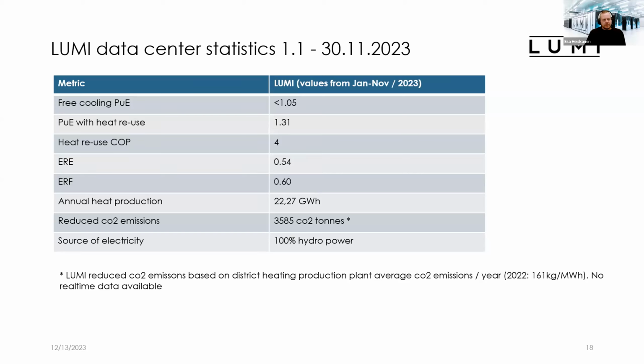Heat reuse COP has been about 4, and we are still doing the optimization and trying to get it better, because in an individual heat pump it can be up to 4.7, and those pumps that are transferring this heat are not consuming that much energy compared to the heat pumps. Annual ERE, calculated for the full year, is 0.534, and in those months that we are not providing the district heating, the PUE and ERE are equal, so those months will increase the ERE value.